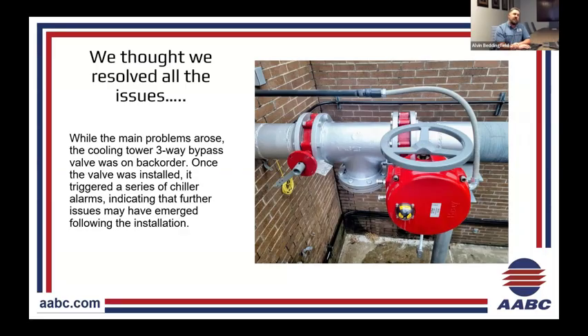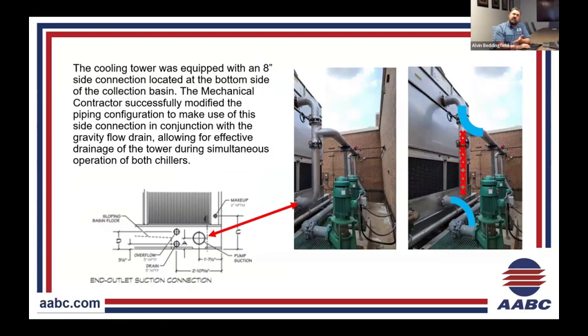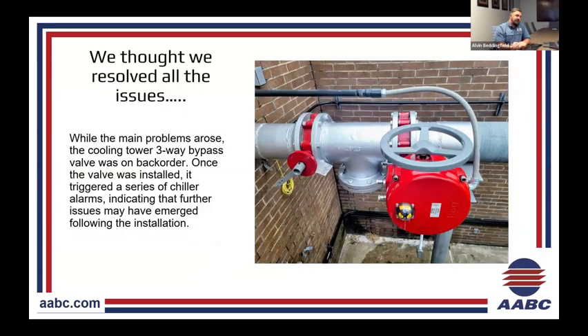Well, while maintaining the main problems of the entire system, the three-way valve, and you can probably see in the back picture, the three-way valve was not replaced. So going back into it, okay, three-way valve's back ordered, tower's running, equipment's running, everything's fine. We're in there balancing the rest of the building. We get called back saying, hey, we keep losing flow. We're getting chiller alarms, chiller alarm, chiller alarm, chiller alarm. I'm like, we cleaned the basin. We took away the overflow issues. What can we possibly keep having?